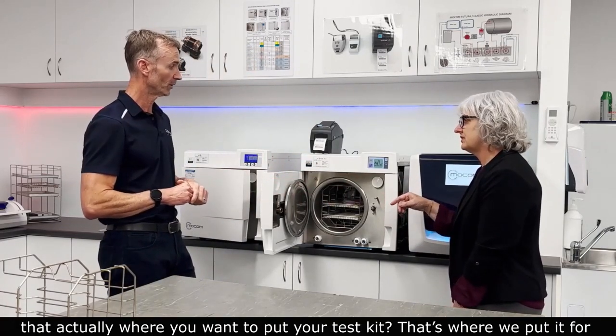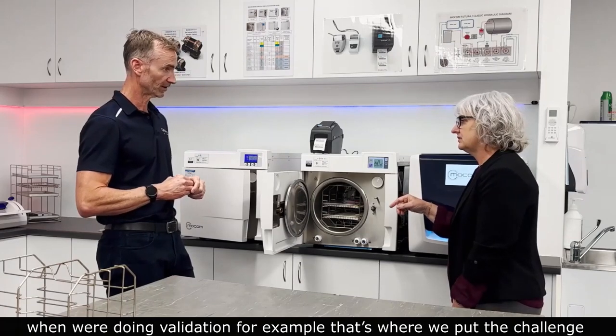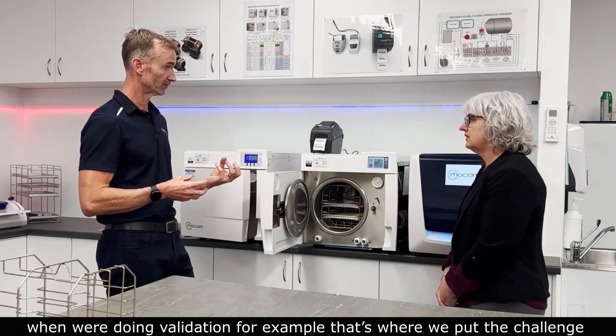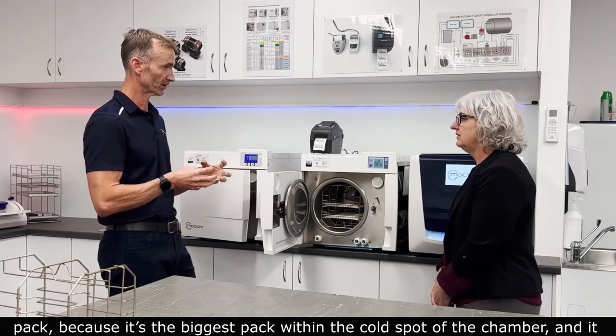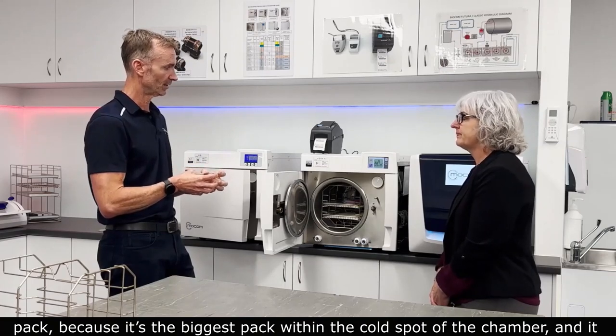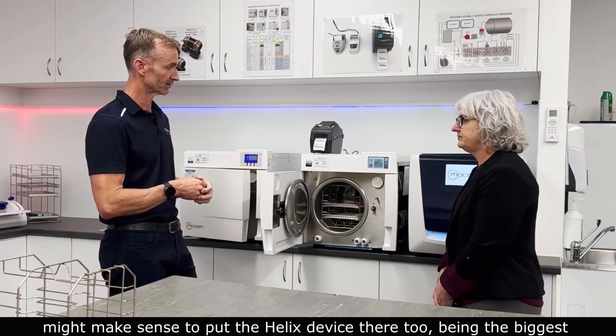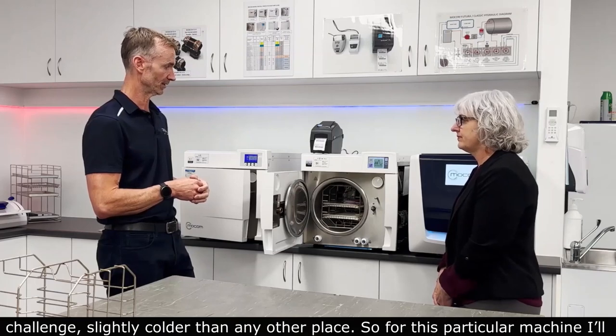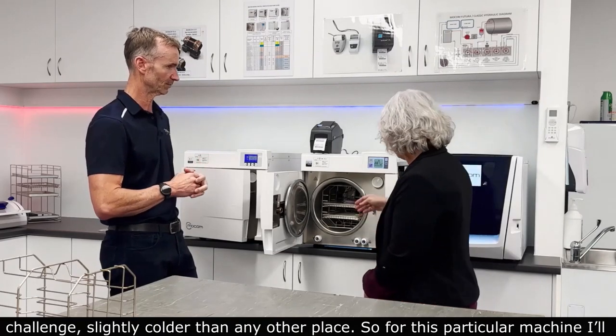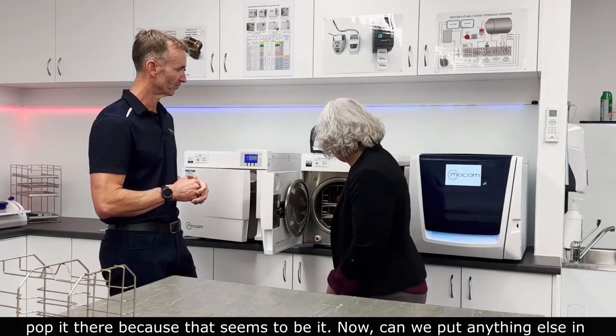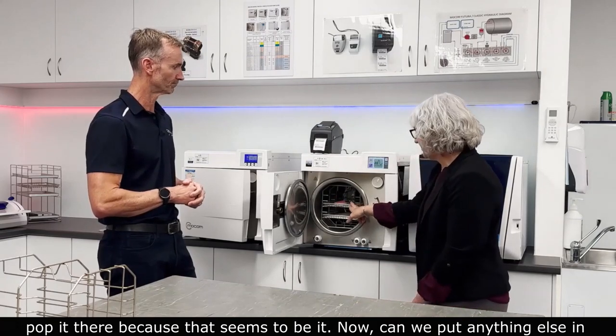Alright, and is that where you want to actually put your test kit? That's where we put the challenge pack when doing validation, because it's the biggest pack within the coldest spot of the chamber. And it might make sense to put the Helix device there too, being the biggest challenge, slightly colder than any other. So for this particular machine, I'll pop it there because that seems to be it.